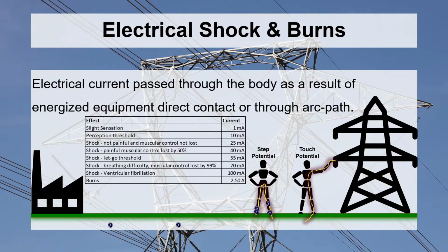If there's a downed conductor or a short from a high voltage line to ground that releases a lot of power, all that voltage in the line is getting dumped into the ground. You can imagine it like water seeping through the dirt — it's not all going to seep instantaneously, so you get a buildup of voltage in that area. The voltage will have a gradient back to the ground source, and whatever that gradient is, that's your step potential. Any of that is going to create current that could potentially flow through your body, up one leg and out the other.